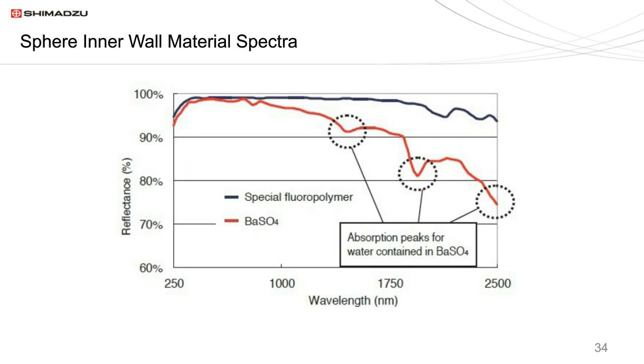Here is a direct comparison of the spectra of Spectralon and barium sulfate. Spectralon never dips below about 94-95%, whereas barium sulfate tends to carry water and can get as low as about 75% around 2500 nm. So a barium sulfate sphere will have more noise associated with it in that area between roughly 1900 and 2500 nanometers — though this doesn't mean it's not usable there; you can adjust instrument parameters to minimize the noise. Both Spectralon and barium sulfate spheres are functional out to 2500 nanometers.